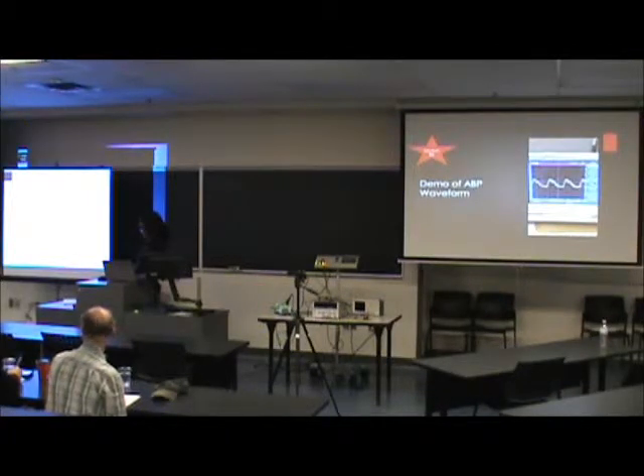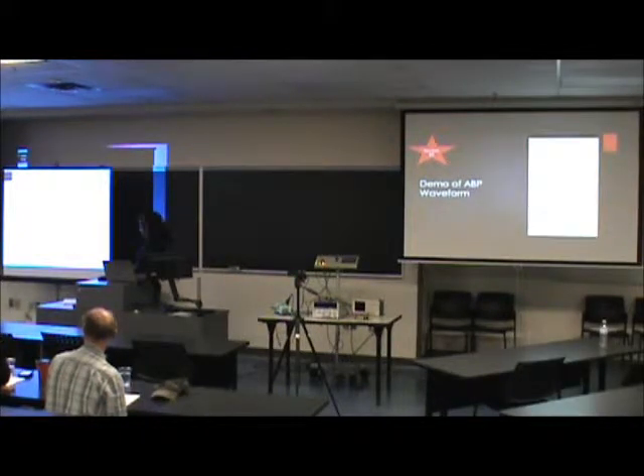To calibrate the device, you can either use an internal calibration system, or you can hook up a patient simulator like a PS420 and verify the waveform. So this is the demo of the patient simulator hooked up to our device. It just displays the dynamic waveform, and you can see it's reproduced it faithfully from the PS420.